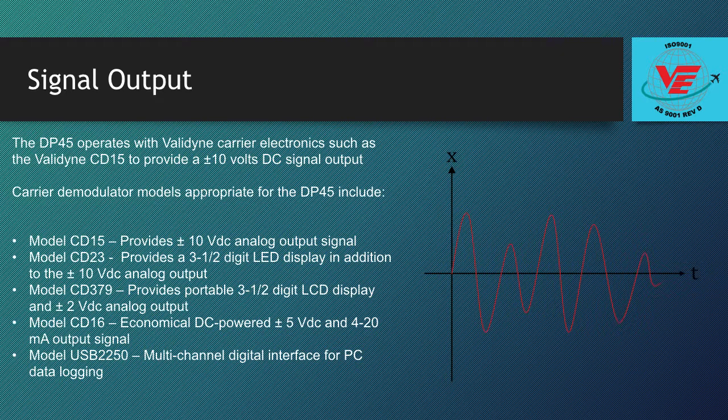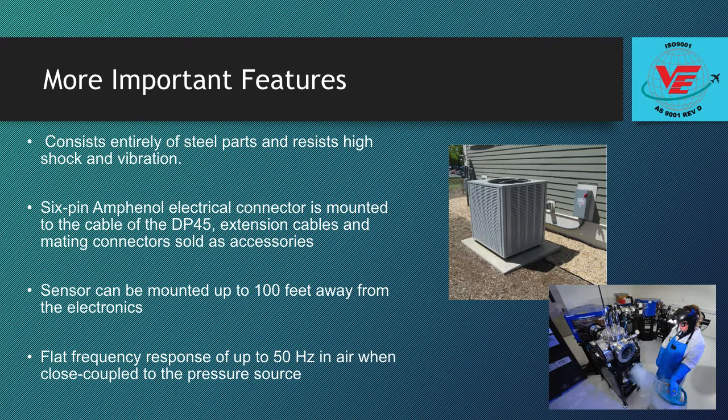Validyne will help you find the best carrier demodulator electronics for your specific application. The DP45 consists entirely of steel parts and resists high shock and vibration. A 6-pin Amphenol electrical connector is mounted to the cable, with extension cables and mating connectors sold as accessories. The sensor can be mounted up to 100 feet away from the electronics.